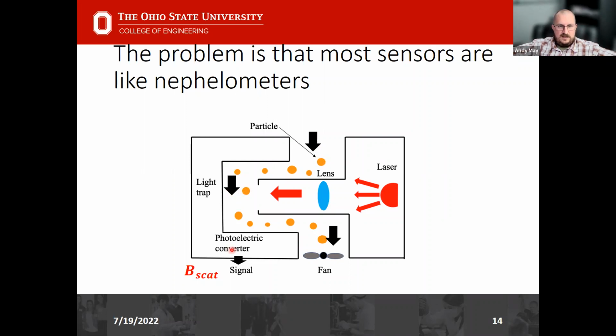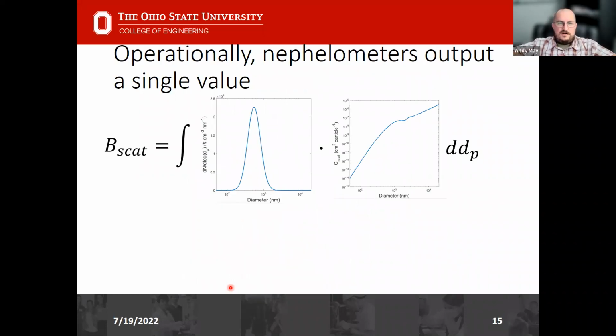If we're thinking about the nephelometer measurement in outdoor air, we call this quantity that's being output a scattering coefficient. What this scattering coefficient really is, is an integral over a range of particle sizes of the product of our particle size distribution and the scattering cross-section for each particle size. We integrate over all the particle sizes, getting a single output value from that measurement. In outdoor air, we can relate the scattering coefficient to a mass concentration of particles by assuming something like a mass scattering efficiency. But again, that's giving us a single mass concentration output.